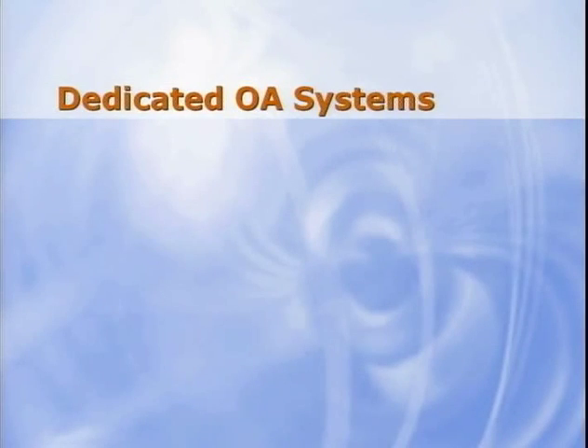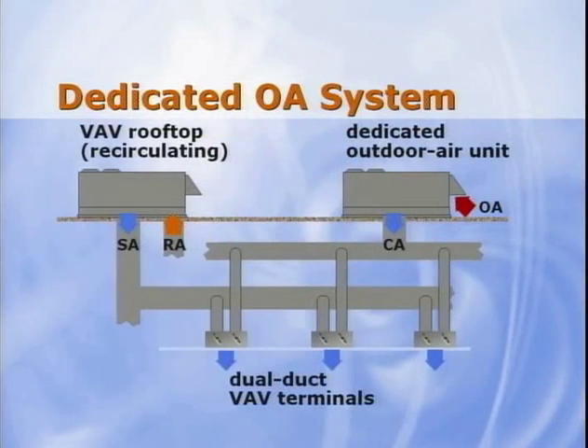Next topic, dedicated outdoor air systems. In a conventional VAV system, the multiple spaces equation from ASHRAE Standard 62 requires the rooftop unit to bring in more outdoor air than simply the sum of the zone ventilation requirements. If, however, a dedicated outdoor air system is used, the dedicated unit conditions all the outdoor air for the system, then delivers it directly to dual duct VAV terminals that serve each zone. The ventilation damper in the dual duct box maintains the required quantity of outdoor air from the dedicated outdoor air unit, while the primary air damper regulates recirculated air from the VAV rooftop unit.